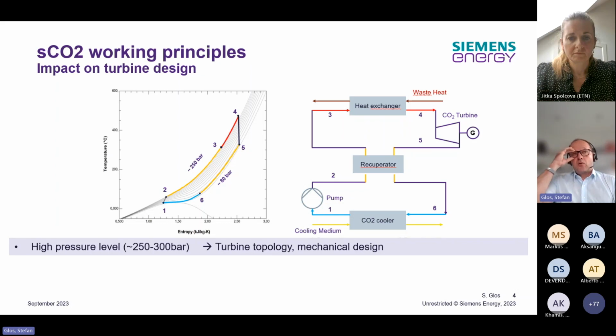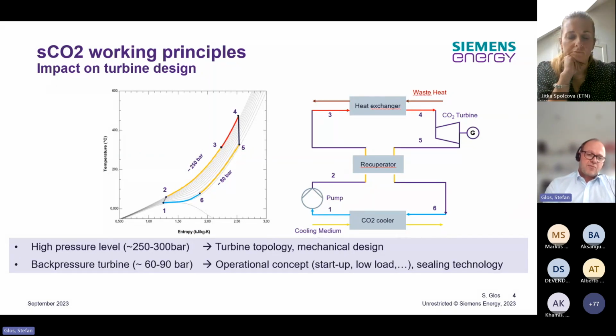When we started to look into that technology, we realized that our barrel type high pressure steam turbines, which are used especially for high pressures in coal-fired power plants, are very suitable for such an expansion. And the second challenge comes from the fact that in sCO2 cycles we always have a back pressure turbine, meaning the lowest pressure level in the system is in the area of 60 to 90 bar.